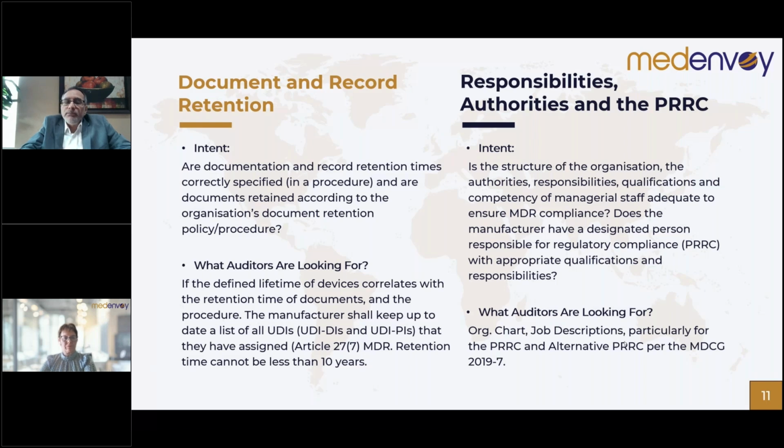In terms of the PRRC, we want to see that you have a clear designation of the individual or person responsible for regulatory compliance. That clearly should be visible through a designation letter and through their job description. The important thing is that it is clearly identifying. So an anecdotal response that I am the PRRC or he is the PRRC is not adequate. We need to see a formal designation in a letter or an organization chart indication, and in addition we see the job description capturing all the elements and requirements associated with the PRRC.